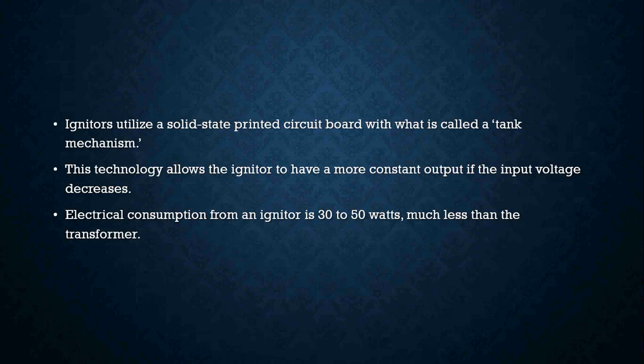Now remember, these types of igniters do not have an iron core in them. They're not two windings wrapped around an iron core like your ignition transformer. These are actually printed circuit boards, and what they usually call those printed circuit boards is a tank mechanism, or that's what they like to refer to them as. This technology allows the igniter to have a more constant output if the input voltage happens to decrease.